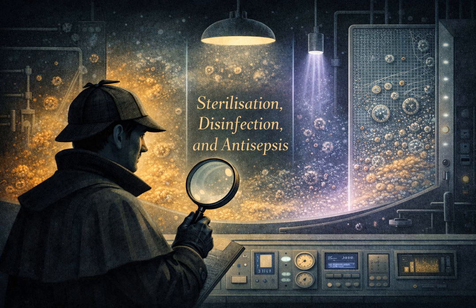Murray makes a really interesting point about the latent heat of condensation here. This is why steam is so much more effective than dry hot air, right? Yes, this is pure thermodynamics. When that 121-degree steam hits a cold surgical instrument, it instantly condenses back into water. That phase change from gas to liquid releases a massive amount of energy, the latent heat, directly onto the steel surface. It transfers heat much, much faster and more efficiently than dry hot air ever could.